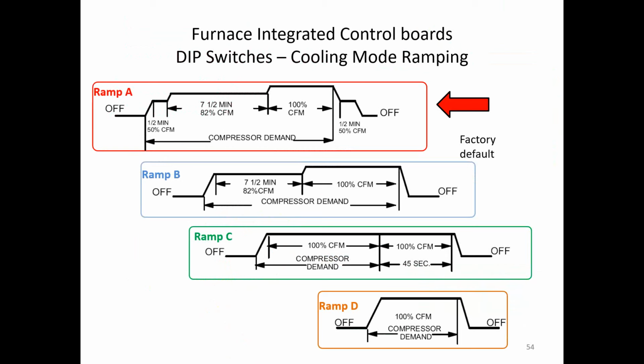The normal run cycle on this unit is going to be 8 to 10 minutes, so we want to make sure we can get as much dehumidification done as possible during a given run cycle. Then if the compressor demand is still there after 7.5 minutes, we still have a call for cooling, whether it be 1st stage or 2-stage, then the blower will ramp up to 100%. After the demand is over, it'll come down to 50% air volume for 30 seconds and then shut off.